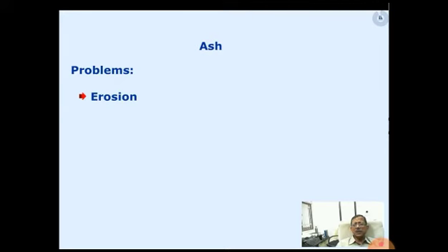Other problem is, of course, if the ash melts, then first of all it can cause slagging. What is slagging? Slagging is nothing but molten ash getting coated over the surface of the tube, right? So heat transfer will be affected, number one. This slagging, if it goes on taking place, it can go on accumulating and it can actually lead to fouling. That is, the flue gas flow will be restricted, the ID current will increase, and all sorts of problems might come.